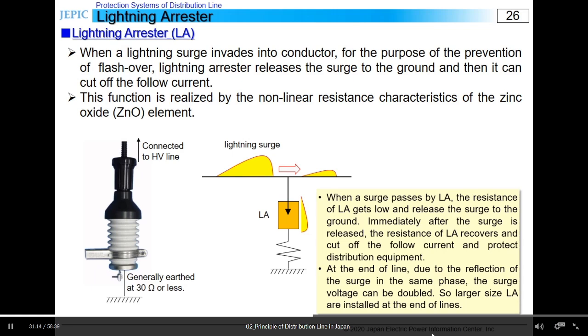Lightning arresters should be installed within four spans, around 200 meters. In addition, at the end of the line, surges reflect in the same phase and the surge amplitude gets doubled. So larger capacity lightning arresters need to be installed at the end of a line.